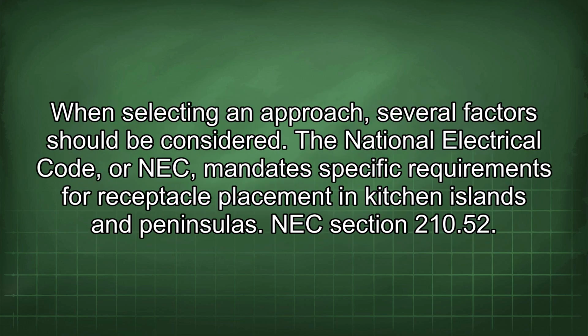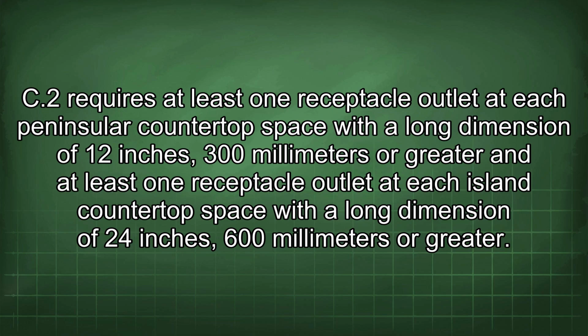When selecting an approach, several factors should be considered. The National Electrical Code, or NEC, mandates specific requirements for receptacle placement in kitchen islands and peninsulas. NEC Section 210.52(C)(2) requires at least one receptacle outlet at each peninsular countertop space with a long dimension of 12 inches (300 mm) or greater, and at least one receptacle outlet at each island countertop space with a long dimension of 24 inches (600 mm) or greater.